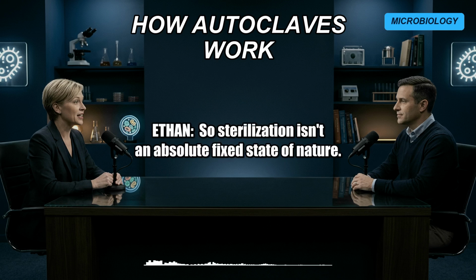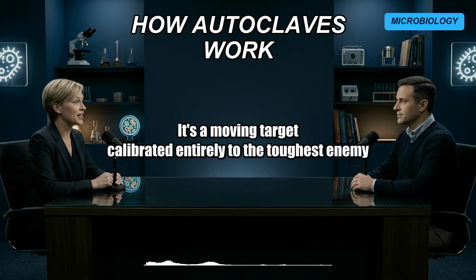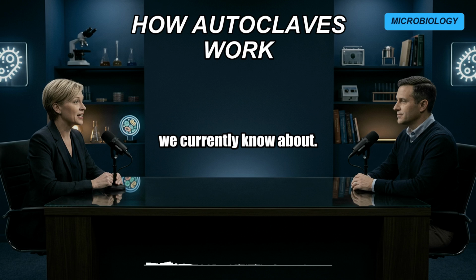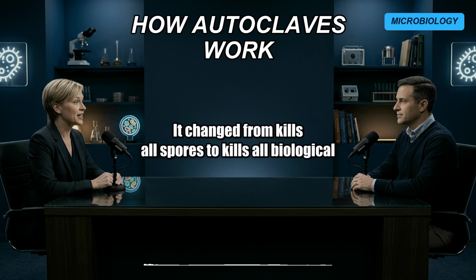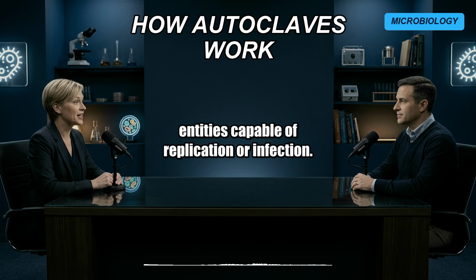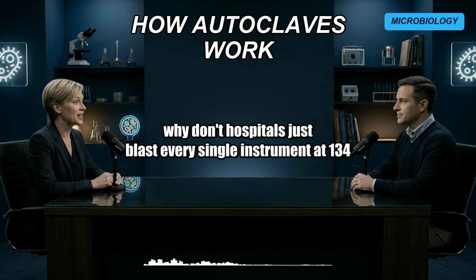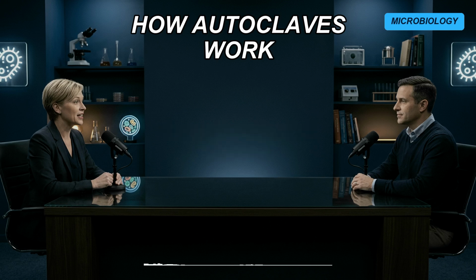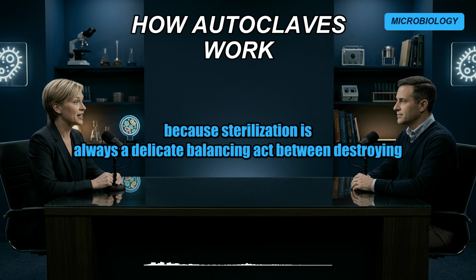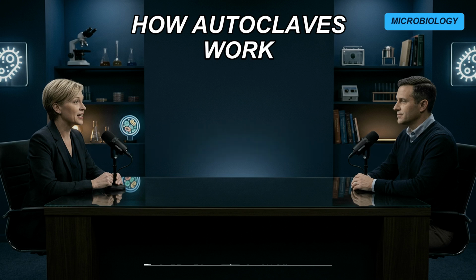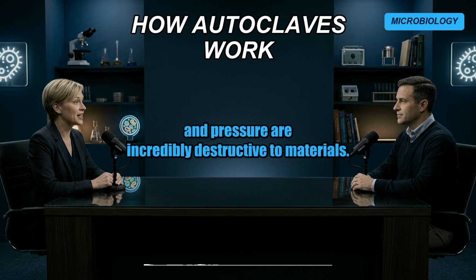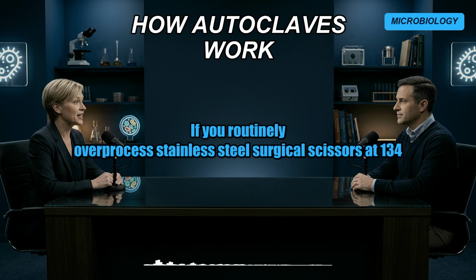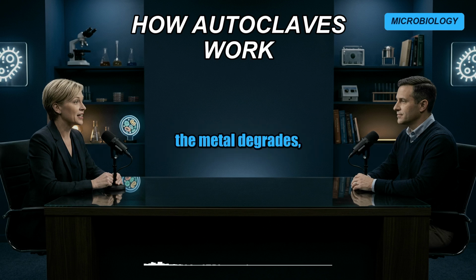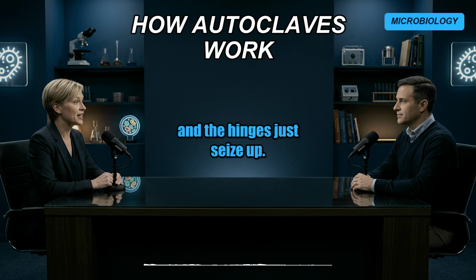So sterilization isn't an absolute fixed state of nature. It's a moving target calibrated entirely to the toughest enemy we currently know about. It changed from kills all spores to kills all biological entities capable of replication or infection. Yeah. But if prions are so dangerous, why don't hospitals just blast every single instrument at 134 degrees for an hour just to be safe? Well, because sterilization is always a delicate balancing act between destroying the pathogen and preserving the tool. Extreme heat, moisture, and pressure are incredibly destructive to materials. If you routinely overprocess stainless steel surgical scissors at 134 degrees for extended periods, the metal degrades, the cutting edges dull rapidly, and the hinges just seize up.